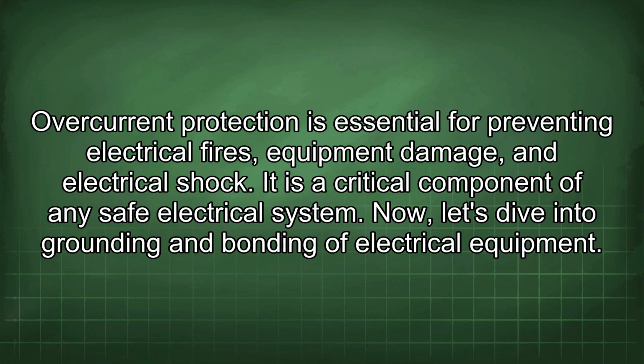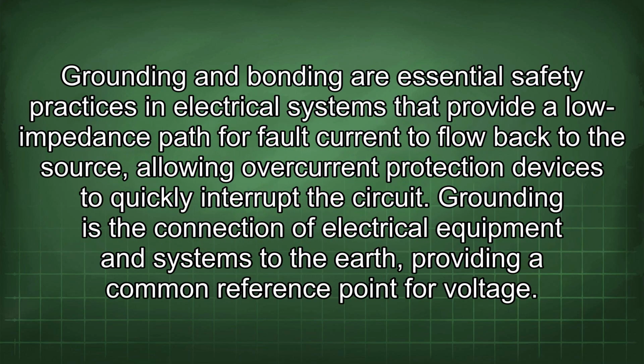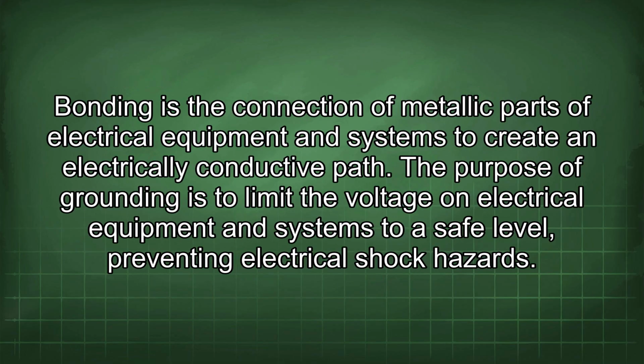Now let's dive into grounding and bonding of electrical equipment. Grounding and bonding are essential safety practices in electrical systems that provide a low impedance path for fault current to flow back to the source, allowing overcurrent protection devices to quickly interrupt the circuit. Grounding is the connection of electrical equipment and systems to the earth, providing a common reference point for voltage. Bonding is the connection of metallic parts of electrical equipment and systems to create an electrically conductive path.